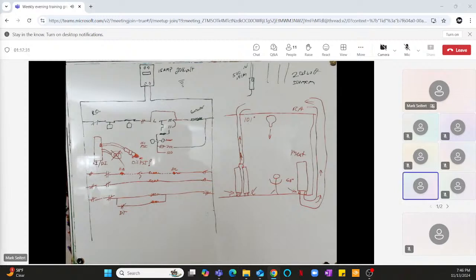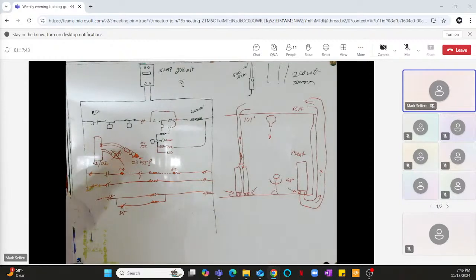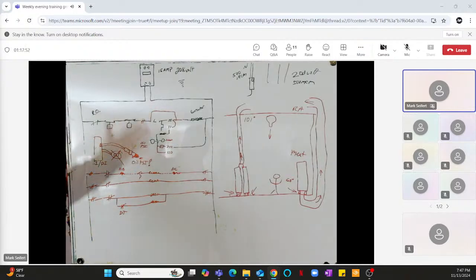So the CT, if it has one, will control the RO? No. The CT is just a proof. The CT is just giving it. Remember, we talked about EMS last time. These are just giving information to the controller. That's all it is. CT is just information. It's not controlling anything. Unless, in the case of a 4-wire, I digress. On a computer, the CT isn't controlling anything. It's giving information. That's it.